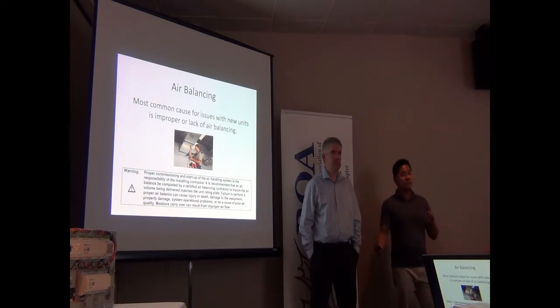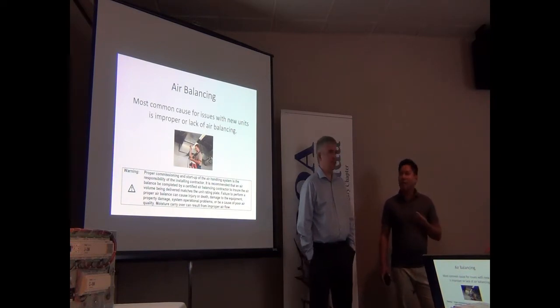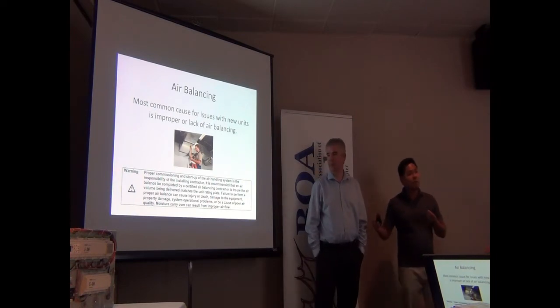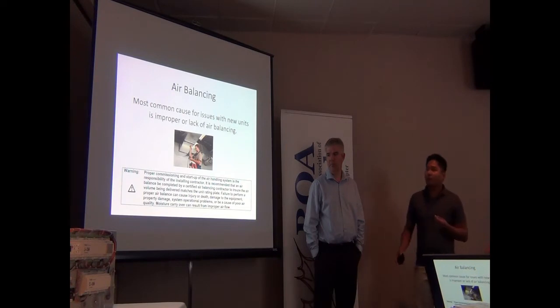We also design for 50% loaded filters, but you've got brand new clean filters in there. It's a bit counterintuitive, but the more airflow and less restriction, you're actually drawing more amps.